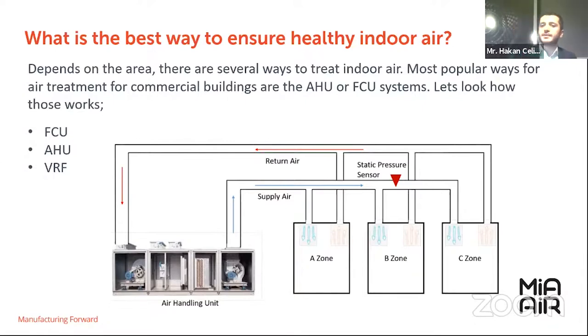Let's check the air handling unit's working principle from this diagram. The main unit sucks air from the outside and blows it inside the room, into the working areas, after some stage of processing like heating or cooling, and sometimes filtration. But because of energy saving concerns, air handling units are designed to use 80 to 20 proportional air for supplying, which means the unit sucks around 20% fresh air from the outside, and circulates 80% of the total air from the inside room.